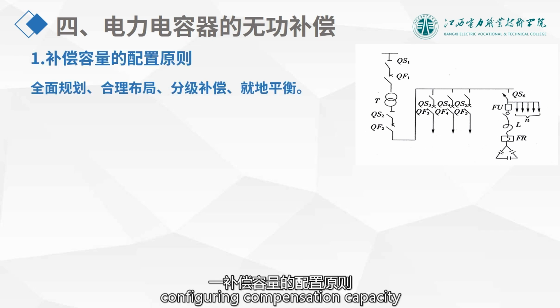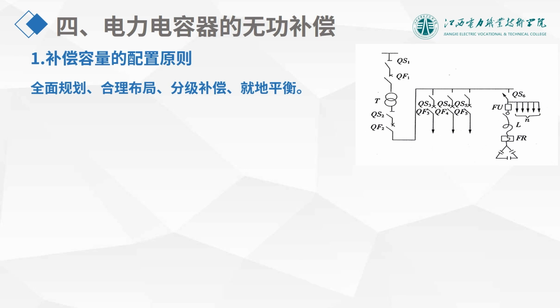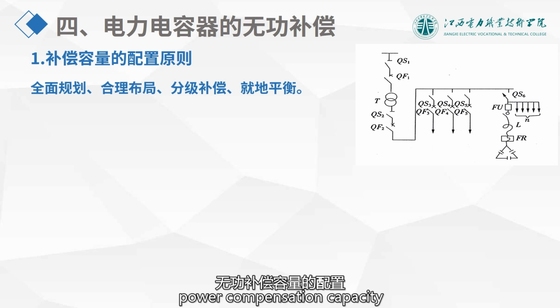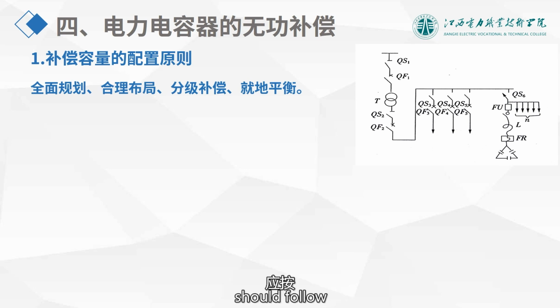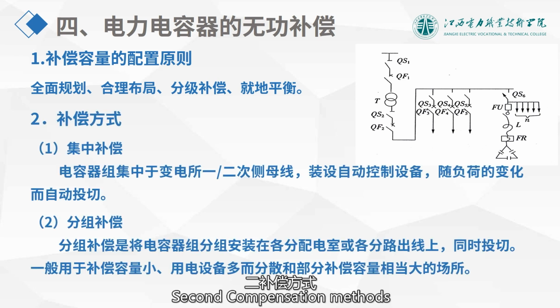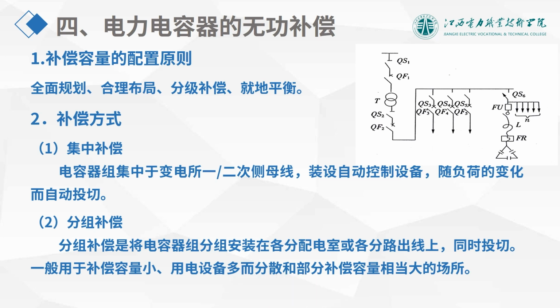First, principles for configuring compensation capacity. The configuration of reactive power compensation capacity should follow the principles of comprehensive planning, rational layout, graded compensation, and local balance. Second, compensation methods. Compensation methods based on the installation location can be divided into centralized compensation and group compensation. As shown in the figure, this is the wiring diagram for centralized capacitor compensation.